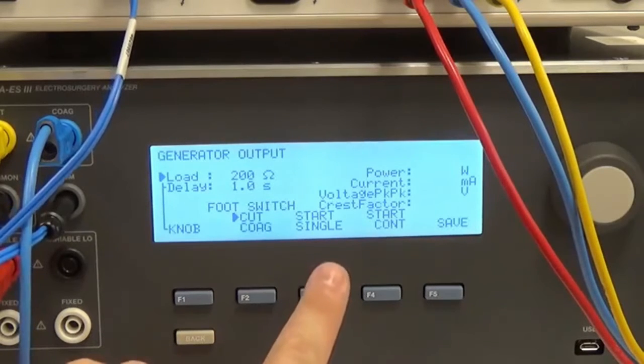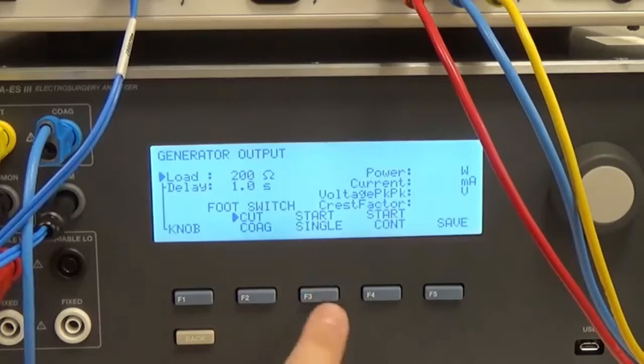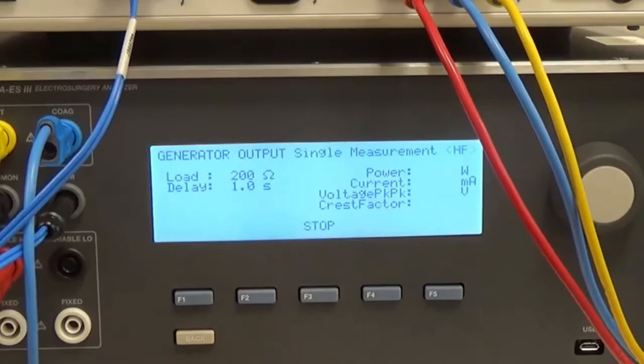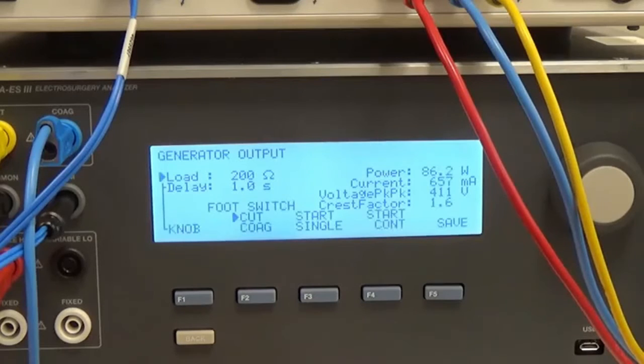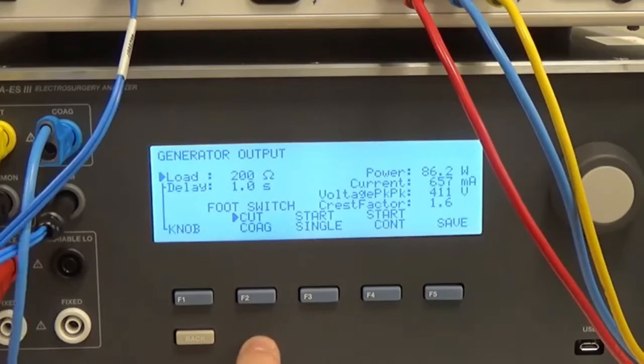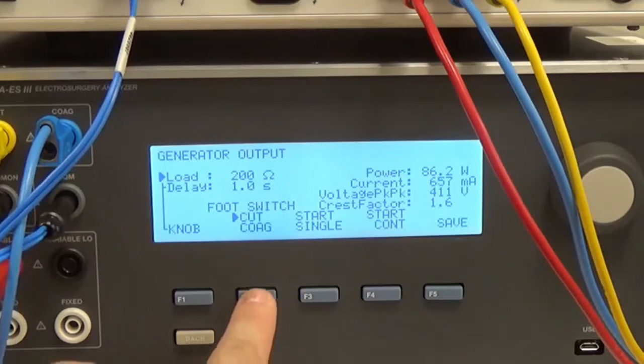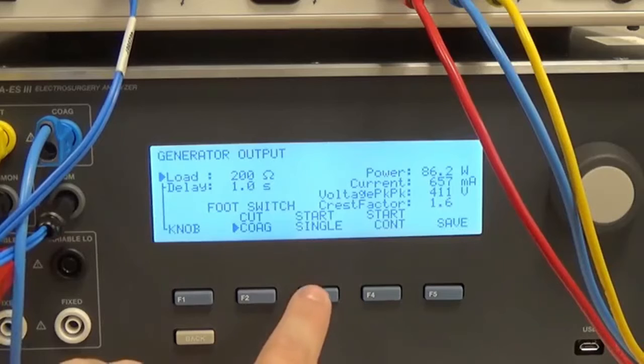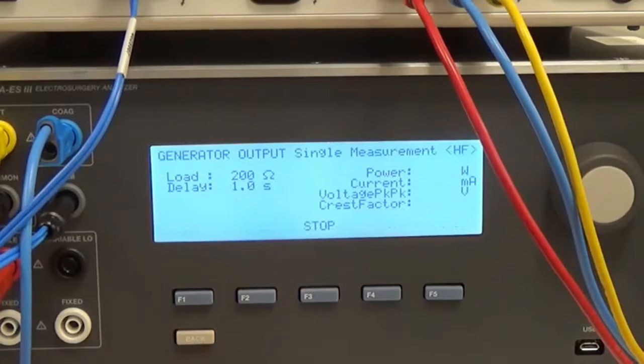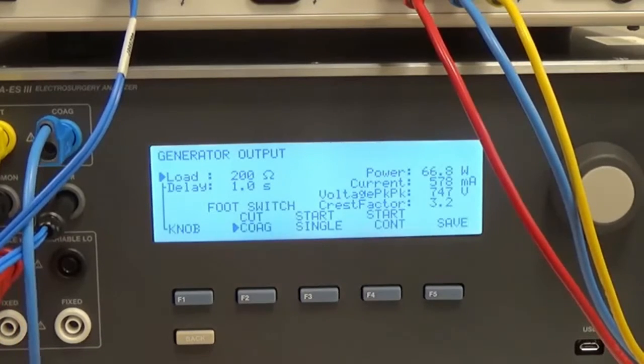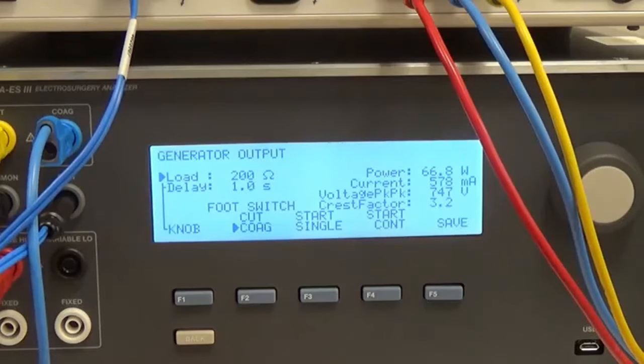Before I start, know that my ESU is actually set to 100 on the cut side. So let's see what wattage we get with 200 ohms, 86.2 watts. If I wanted to measure the coag side, just select coag here and start single again. My coag was set to 80 on the ESU, and you can see I have the wattage of 66.8 for power. Our current's at 578, peak-to-peak voltage at 747, and a crest factor of 3.2.